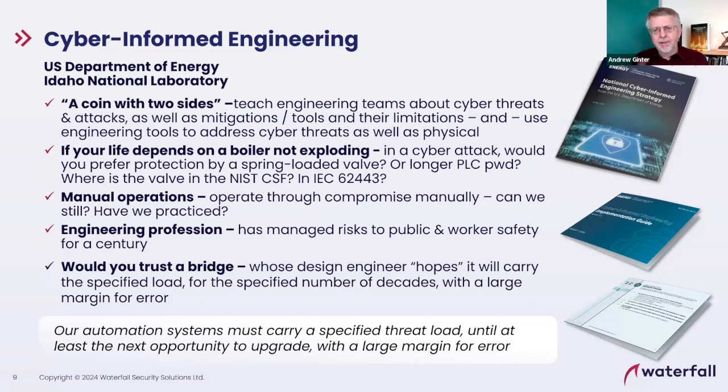But here's the thing. Where is the overpressure valve in ISO 27001, the cybersecurity standard everyone uses for IT? Not a mention of it. Where is it in the NIST cybersecurity framework? Not a hint of it. Where is it in the industrial 62443 cybersecurity standards? Not a word of it. The overpressure relief valve is not a cybersecurity mitigation. It's an engineering tool for managing physical risk, the risk of an earthquake crimping the output piping on the boiler and overpressurizing the boiler.